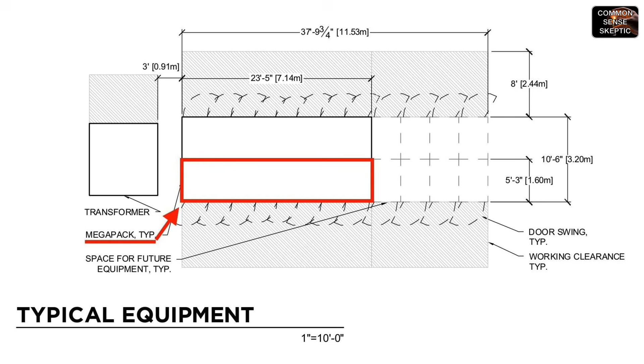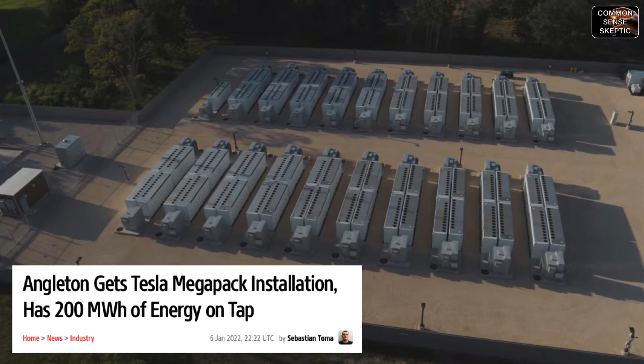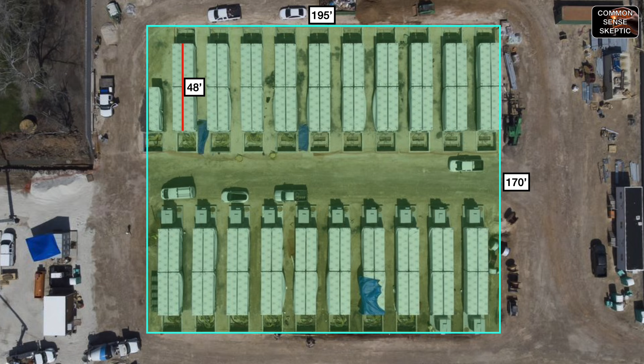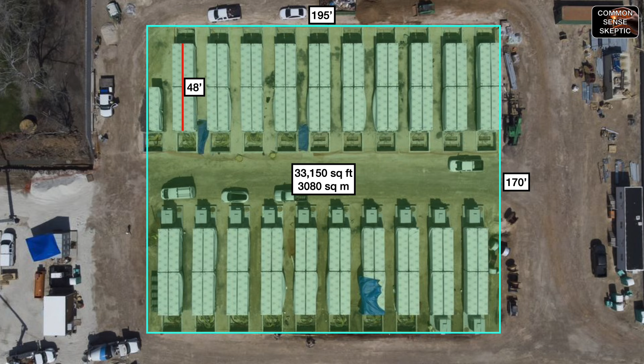A Megapack measures around 24 feet long, around 7 meters, and 5 feet or 1.6 meters across. Each one weighs 23 tons and can hold 3 megawatt hours of energy. Here's a drone photo for one of the installations that Tesla built for Angleton, Texas, a 200 megawatt hour facility. These megapacks are positioned in groups of 4. If we use the length of a double unit at 48 feet to extrapolate the dimensions of the footprint, we find that this footprint required for 80 units is 195 feet across and 170 feet deep, giving a footprint of 33,150 square feet, about 3/4 of an acre, or 3,080 square meters, 0.308 hectares.